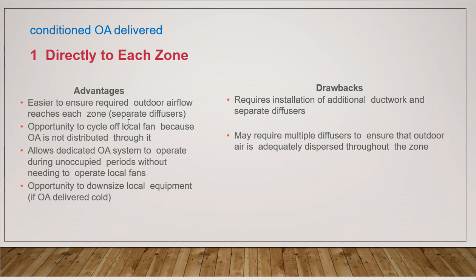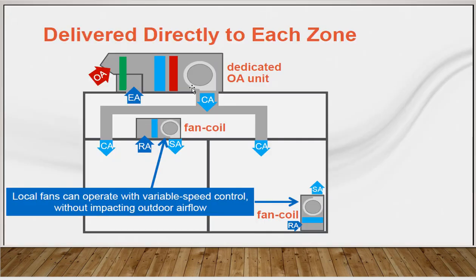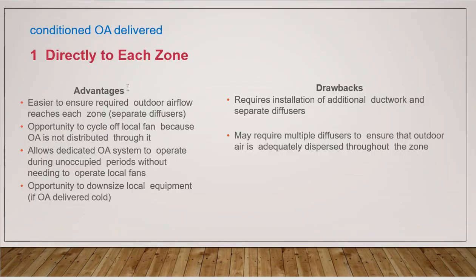Let's have a look at the advantages of directly to each zone. Directly to each zone means it is ventilated directly to the zone without the need to be connected to the fan or the fan coil or the terminal unit. So it is simply directed to each zone. It is easier to ensure required outdoor airflow reaches each zone. There is an opportunity to cycle off the local fan because OA is not distributed through it. It allows the dedicated OA system to operate during unoccupied periods without needing to operate local fans. There is an opportunity to downsize local equipment. The disadvantages: it requires installation of additional ductwork, and separate diffusers, and may require multiple diffusers to ensure that outdoor air is adequately dispersed through the zone.